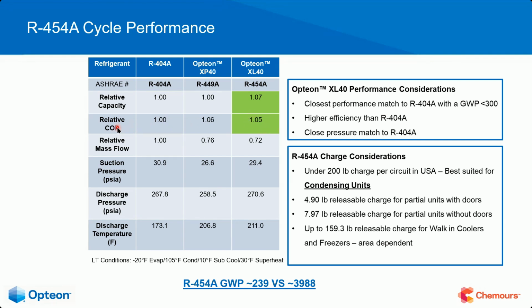Now, what is COP? For those of you who don't know. Well, it stands for coefficient of performance, but in the Don Gillis version or definition, I'm going to say it like this. It's simply put, it's how much capacity you're getting out of your evaporator compared to how much energy you're using on your compressor or the system as a whole. So it takes the capacity and the energy used in the system as a whole and puts it into the ratio. This is the important number they use like for equipment designers. The COP is everything to them. That's kind of what they start with, all right? And then everything else follows behind it. Relative mass flow, starting at 1, then we go to 0.76 for 449A and 0.72 for new equipment, 454A.